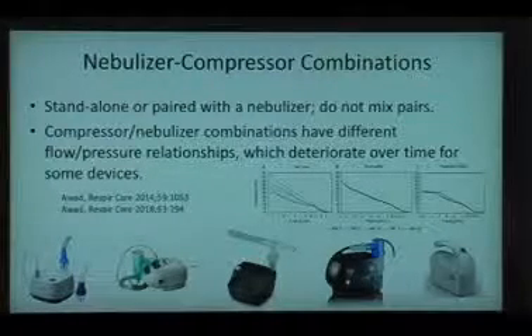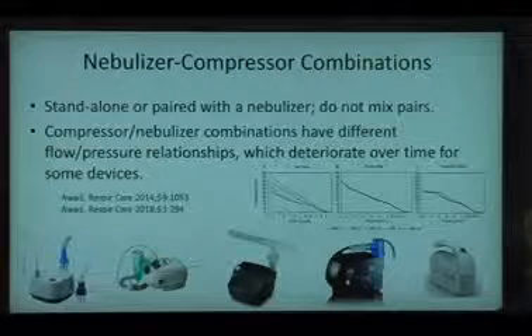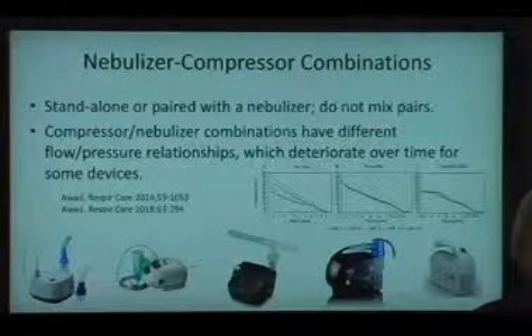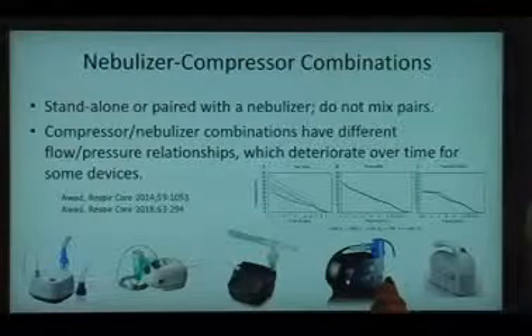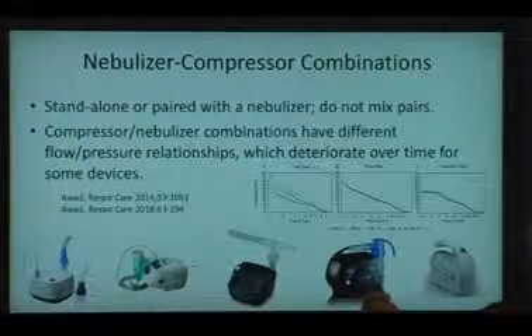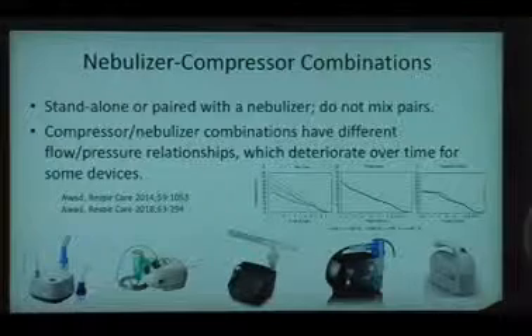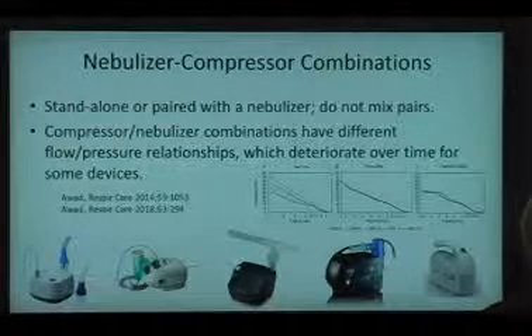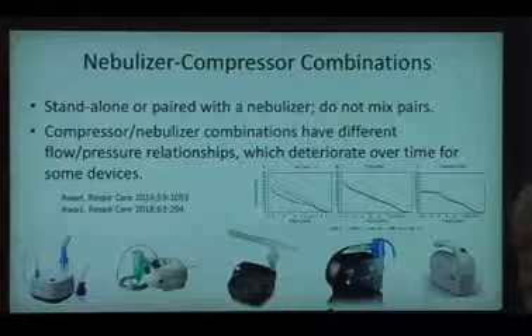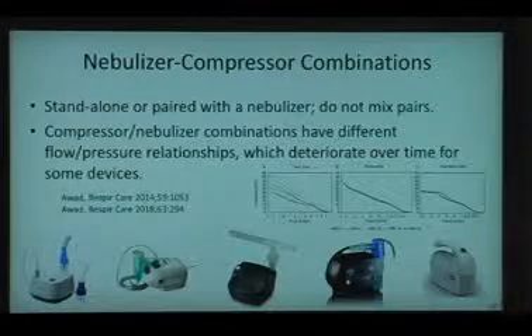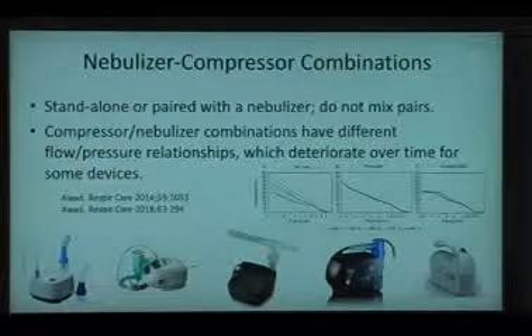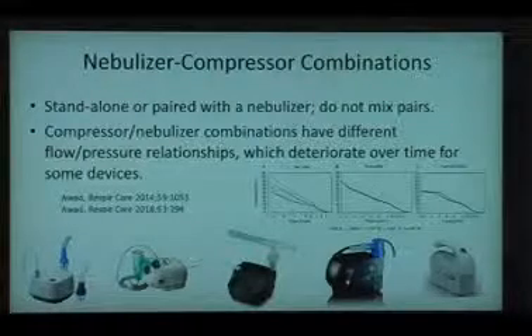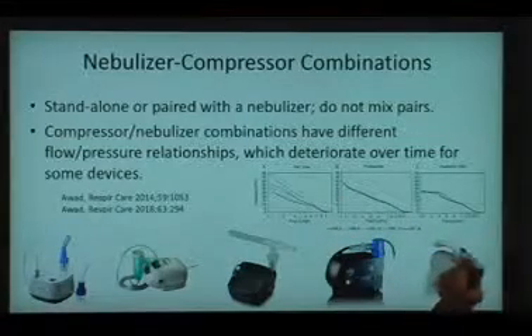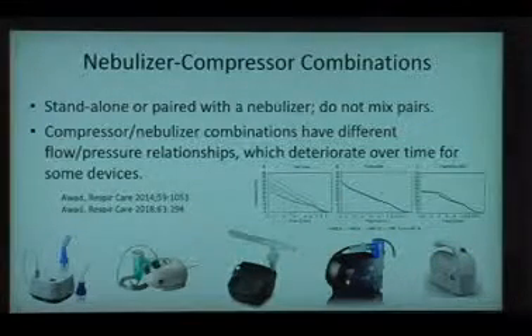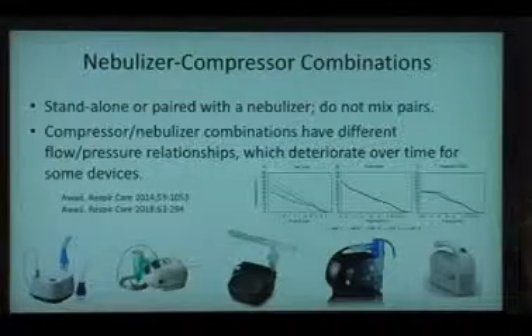When we practice in the hospital, we usually just hook the nebulizer up to the flow meter, so this isn't something we have to think about. But it is an issue for why a patient, for example, might get admitted to the emergency department because their compressor isn't working very well, so they're not getting their medication as they should. So that's more the function of the compressor, not the nebulizer? Correct. The deterioration is the result of the compressor over time not being able to generate the same pressure and flow.